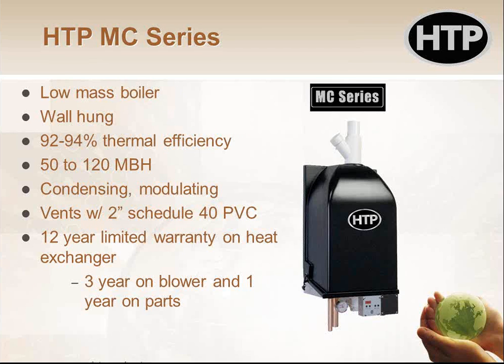So some of the specific boilers we would be looking at, this particular one is an HTP Contender. Now it's called the MC series. They renamed it. It's a low mass boiler, so it requires primary, secondary. This guy's a wall hung, typically 93% efficient or so, depending on the exact size of it. Sizes go from 50 to 120. It's fully condensing, right? So that means I've got to have the PVC venting, Schedule 40 PVC venting. I've got to have a condensate drain, somewhere to put this condensate down.